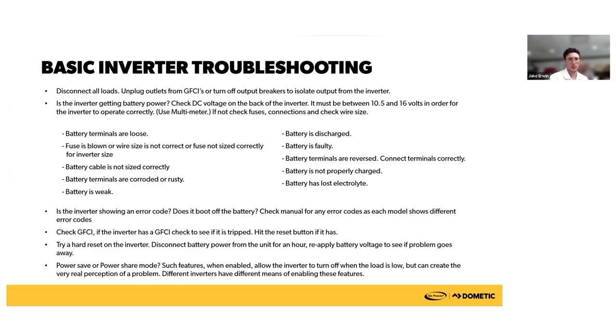Is the unit actually getting power? So start by disconnecting loads, unplug the inverter from anything it's connected to, turn off breakers to isolate the inverter output to itself, and then check, is it getting battery power? To do that, you always want to check directly at the back of the unit. So check DC voltage directly at the back of the inverter. Don't check it at the batteries, check it directly at the unit. That way you know, okay, is this unit actually receiving any 12-volt power from the batteries?